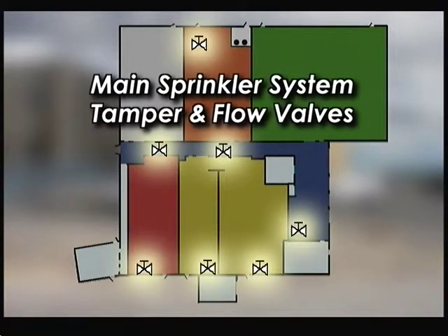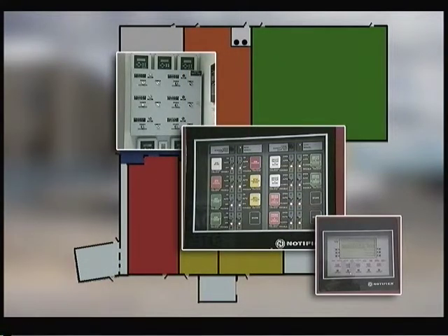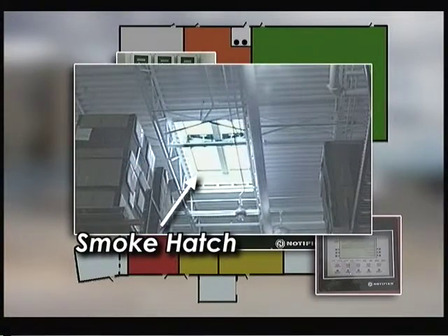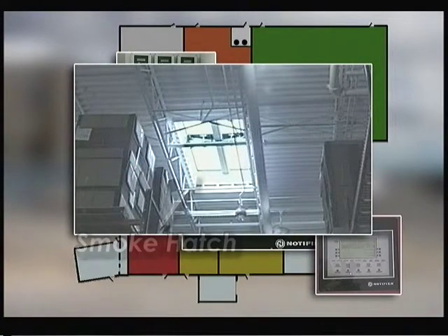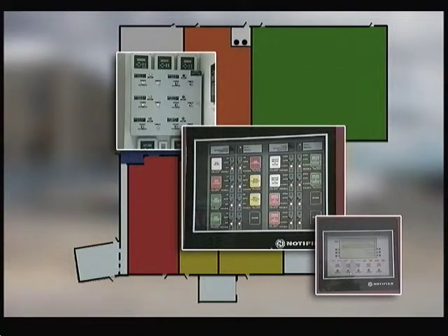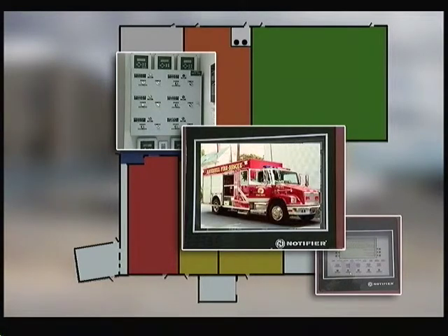The main sprinkler system and riser valves are provided with automatic monitoring of pressure, tamper, and flow status at the zone valve assembly. The mechanical, electrical, and plumbing, or MEP systems, allow the fire department to manually control the systems from an isolated control panel. From here, one can manually release smoke hatches and mechanically ventilate a room with an incident ongoing. One can also choose to do nothing and let the building's systems control the situation. The safeguards give the fire department a window of time sufficient enough so lives are not put in harm's way if a problem arises.